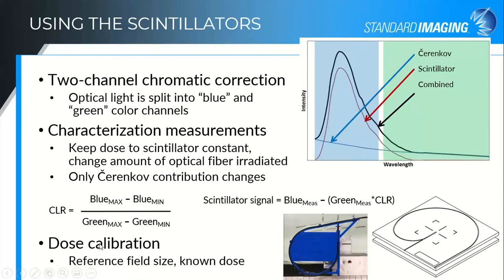If you want to do a dose calibration and cross-calibrate with a known dose — rather than just doing relative measurements like output factors — you can give it a known dose with a reference field size. The 10 by 10 is marked out on the positioning slabs that come with the W1. This really just becomes a scaling factor and unit conversion applied to the calculation, so instead of nanocoulombs or picocoulombs collected, it turns into a centigray based on your characterization and calibration of the device.